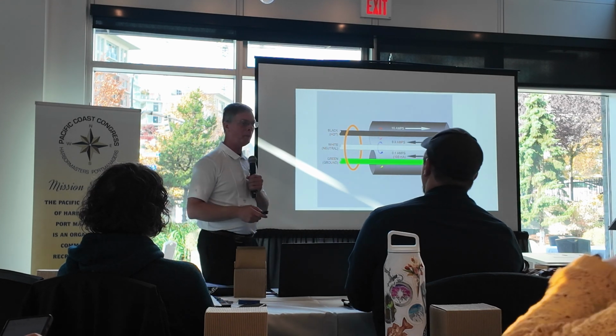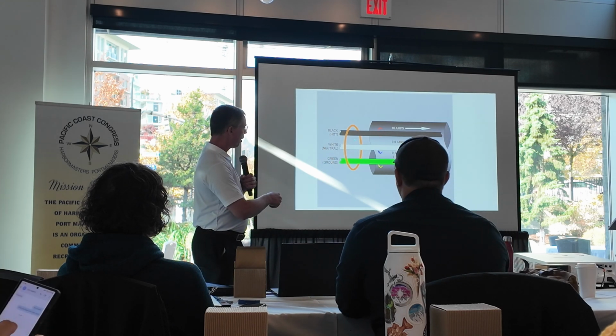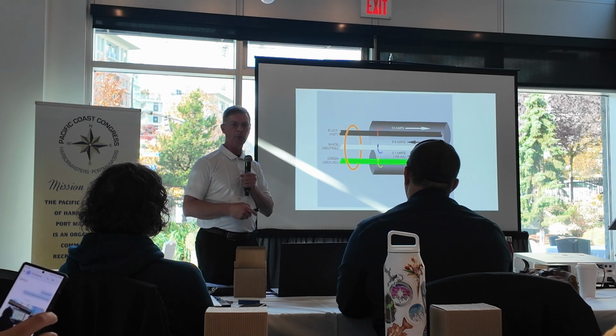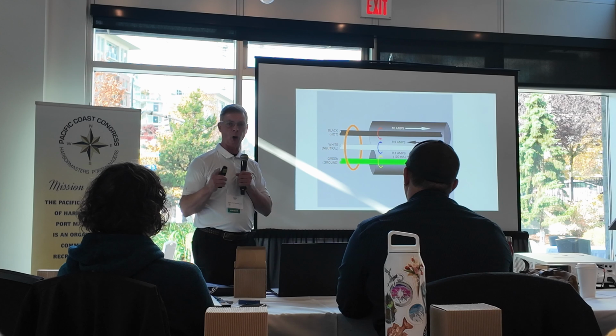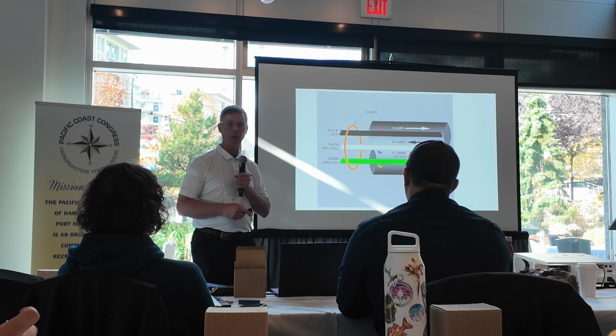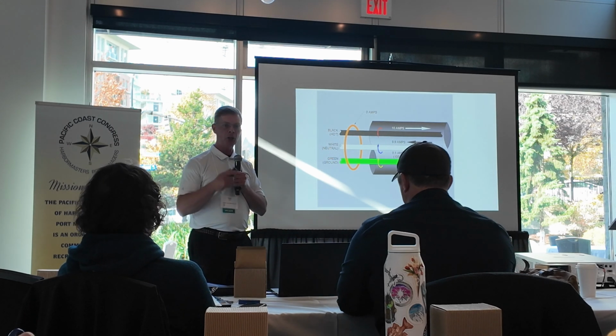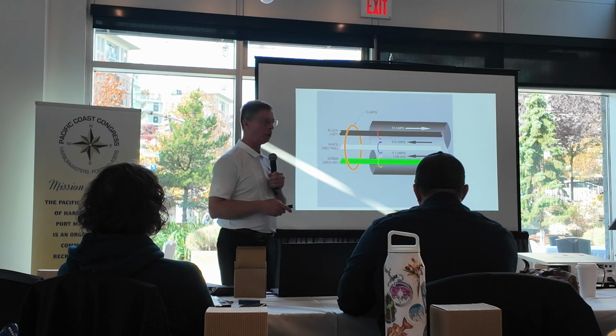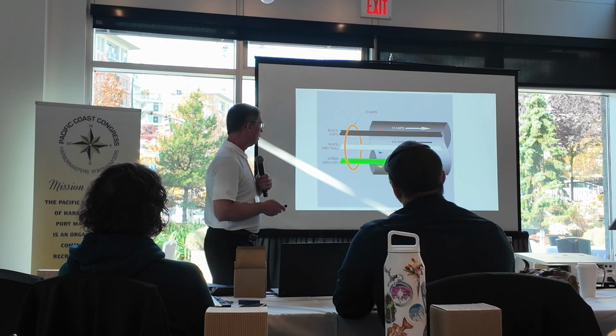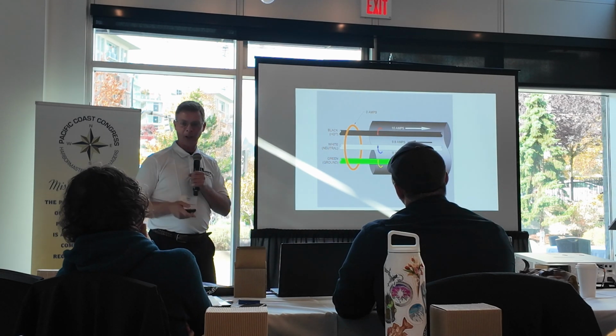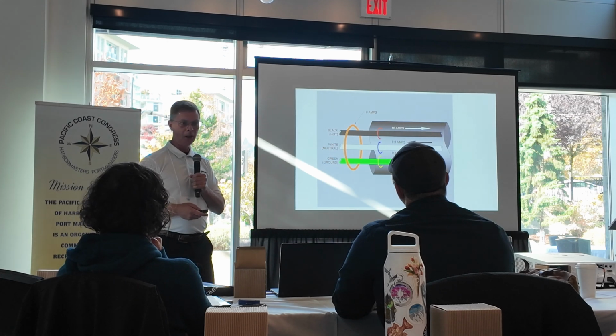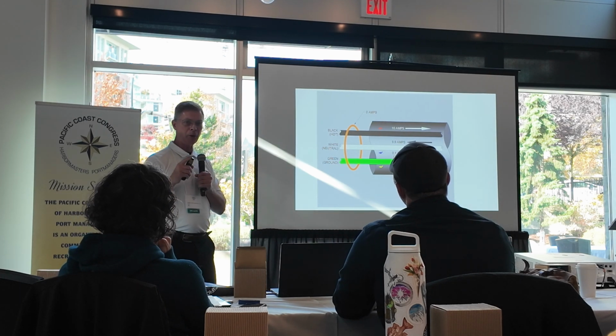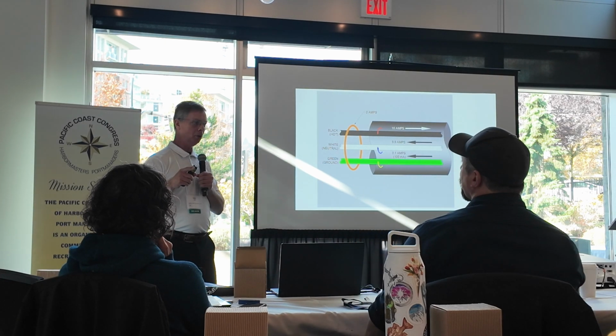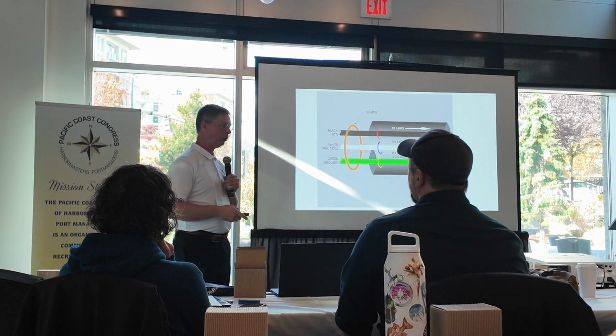Yep. His comment was that this would be if all 3 wires are going through that CT. You'd never see the leakage current on the ground wire, and in fact, I'd read 0 milliamps. No matter how much I inject to the ground wire, it'd read 0. Okay? Now, does that click in your head a little bit? Okay? So, understanding that right-hand rule in the magnetic field is the key to understanding AC leakage current.